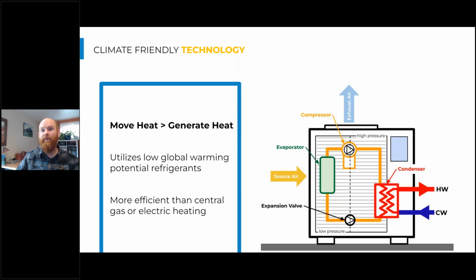So now we can dump a bunch of that heat that we extracted from our source of air into hot water, and that happens in our condenser, which is a refrigerant to water heat exchanger. Once again, it's a heat exchanger, and we're just dissipating that heat into our domestic water. And then it's a cycle. So we need an expansion valve to get back to the first state of that cycle. This is allowing the refrigerant to expand where we contracted or pressurized the refrigerant up at the compressor. This is also modulating the pressures across it so that we're always targeting a certain discharge water temperature here.